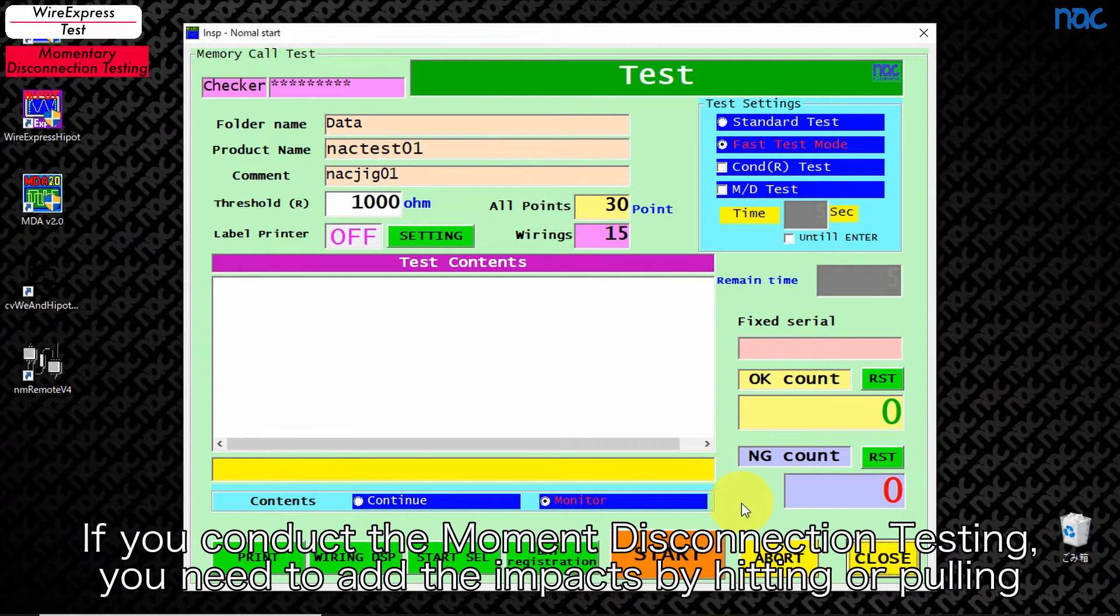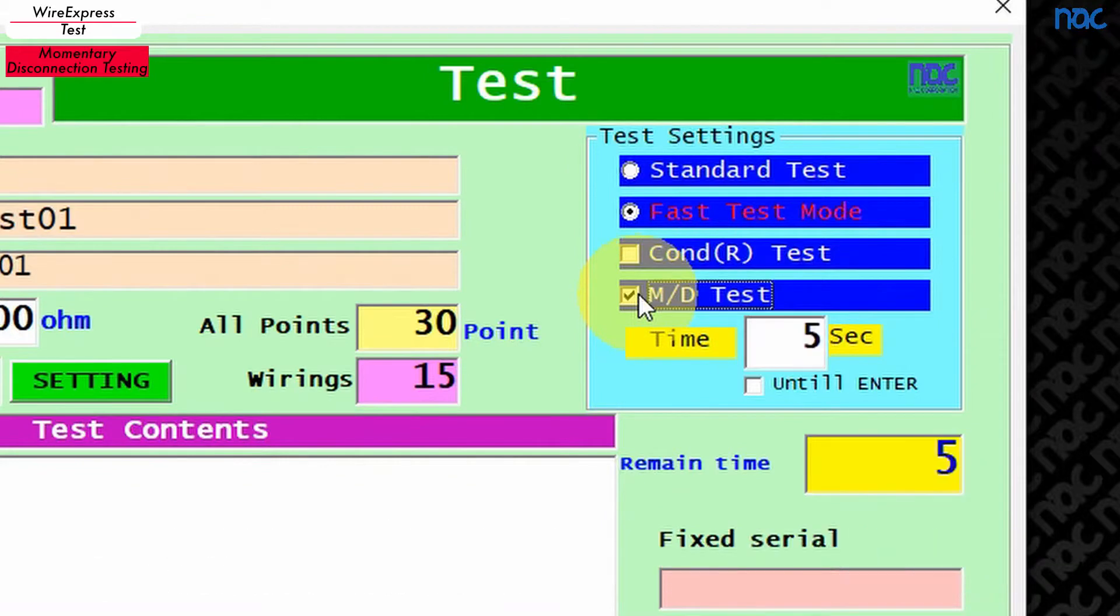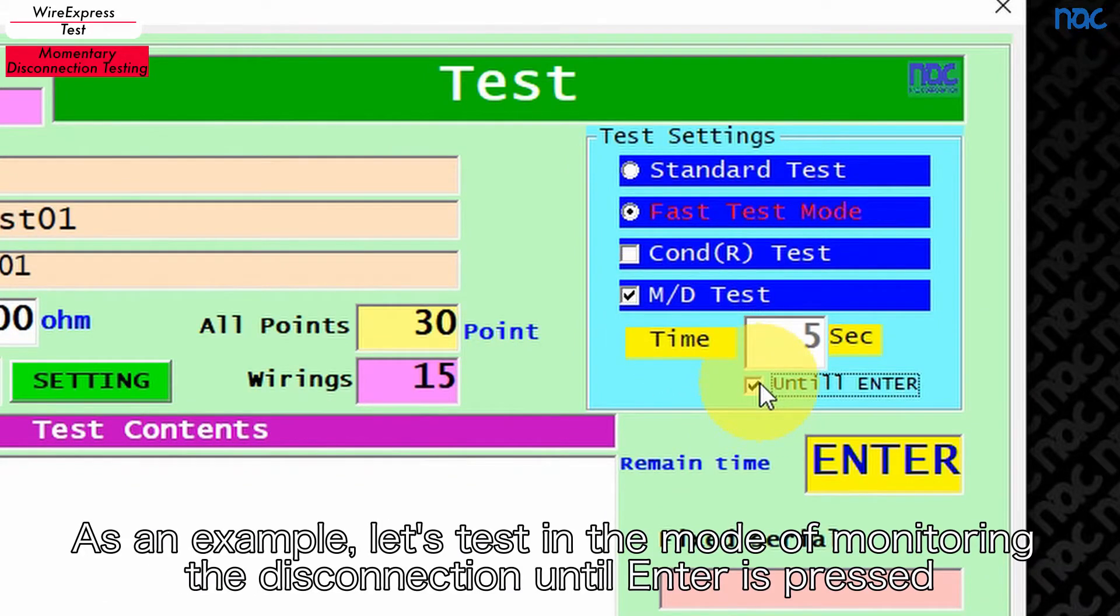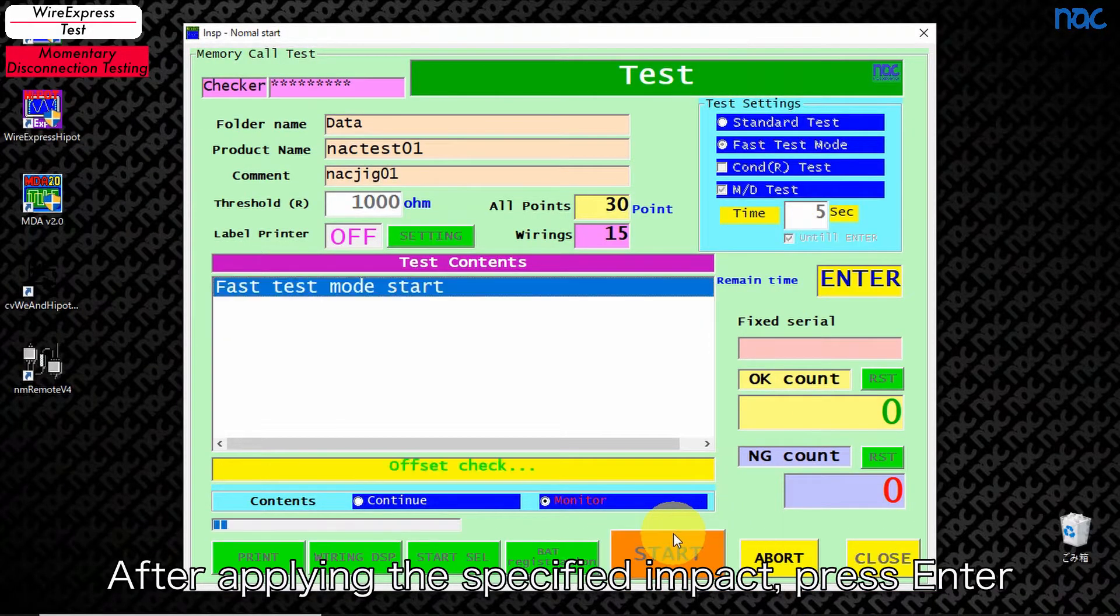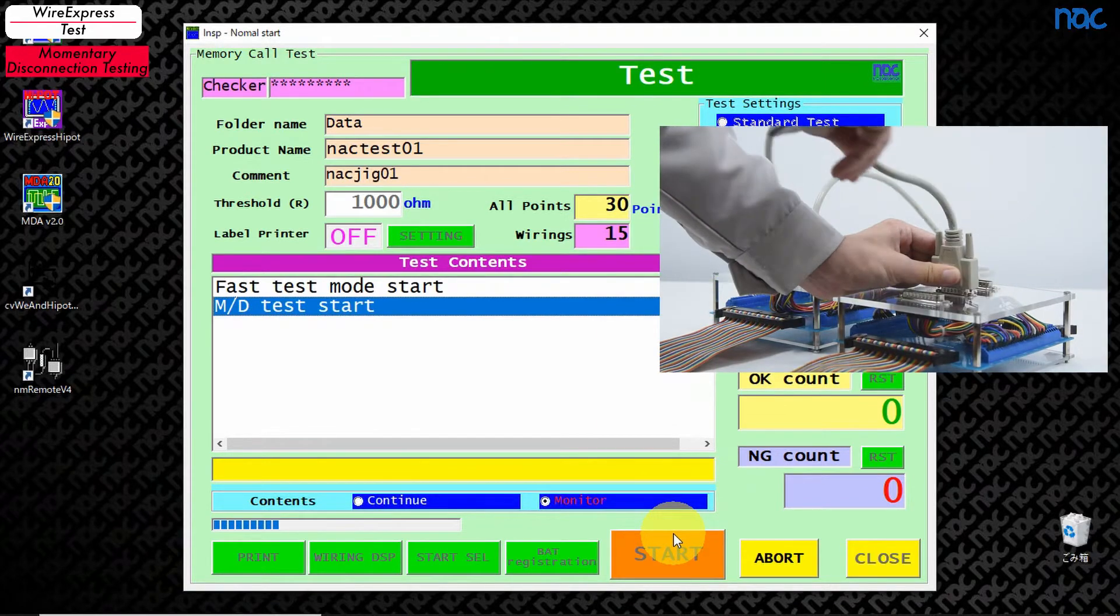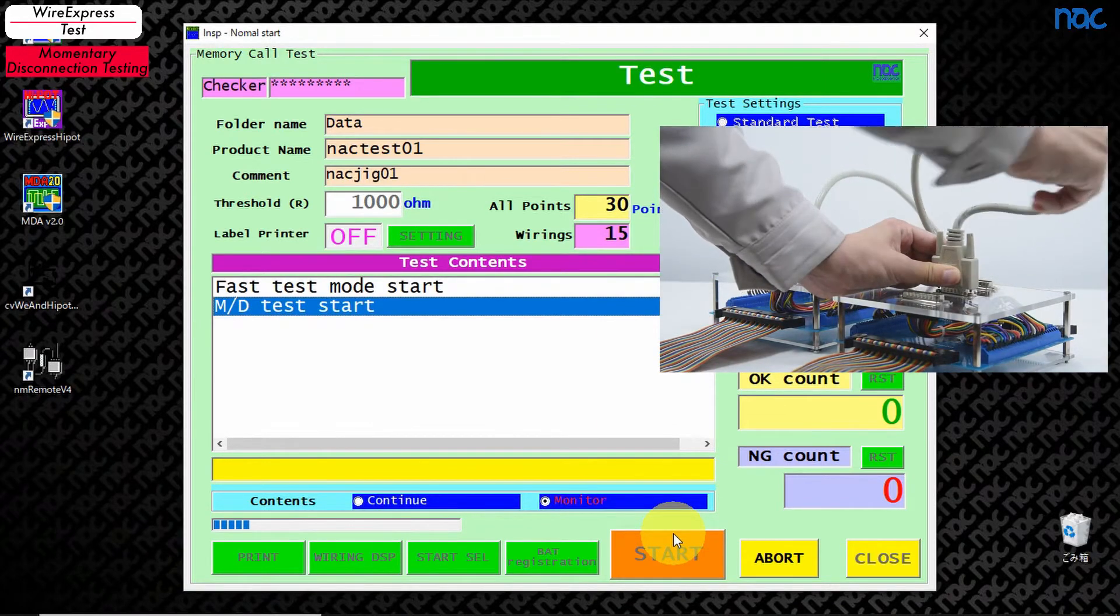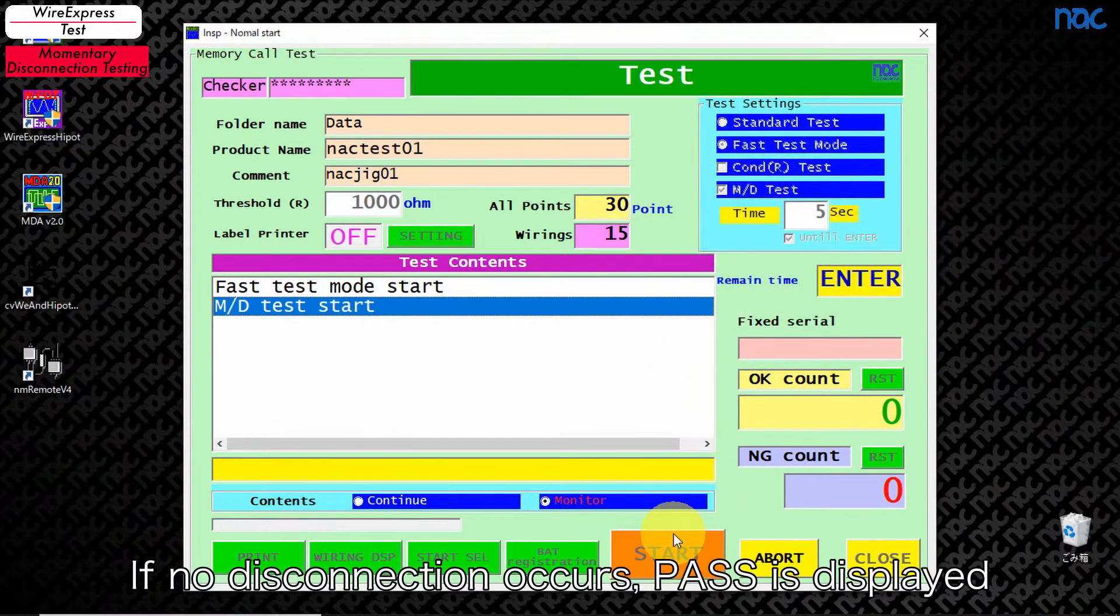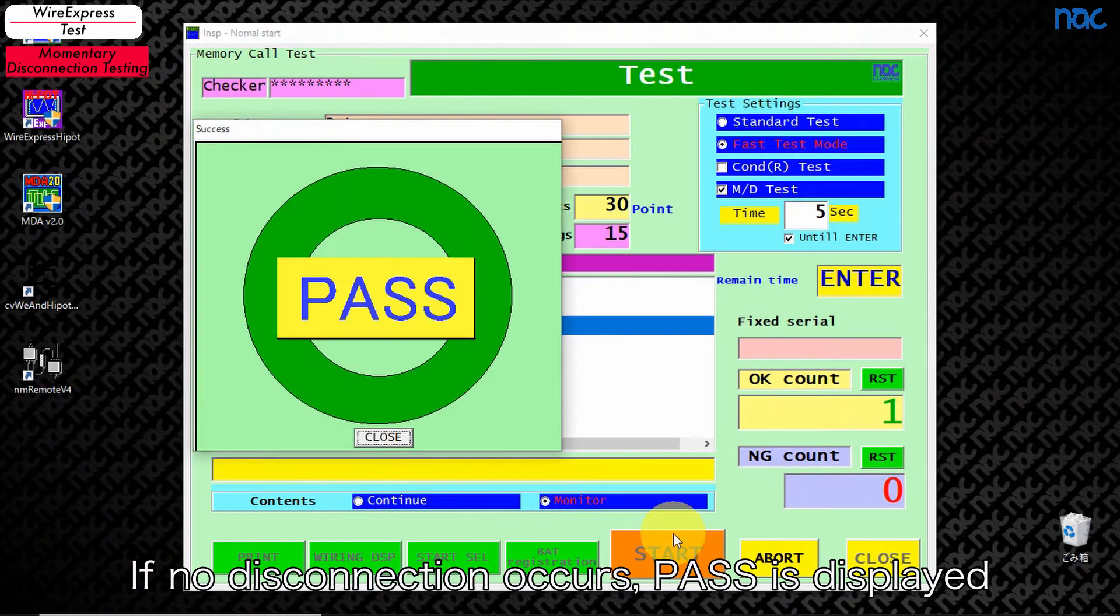If you conduct the moment disconnection testing, you need to add the impacts by hitting or pulling. As an example, let's test in the mode of monitoring the disconnection until enter is pressed. After applying the specified impact, press enter. Moment disconnection test. If no disconnection occurs, pass is displayed.